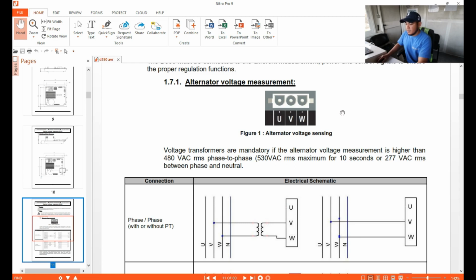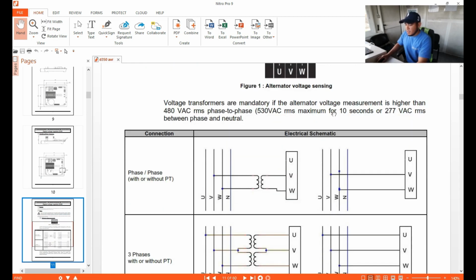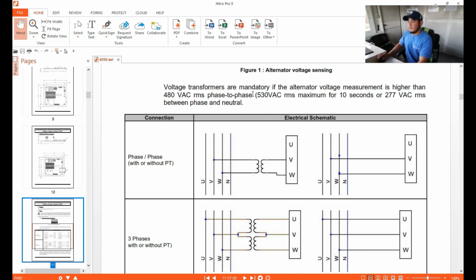Okay, so UVW. It is stated here that the voltage transformer is mandatory if the alternator voltage is higher than or equal to 480 volt AC RMS, phase to phase, which in our terms is line to line. So if you exceed 480 volt AC, you need to install a transformer to ensure it will work properly. The maximum is 530 VAC RMS for a maximum of 10 seconds, or 277 VAC RMS between phase and neutral.